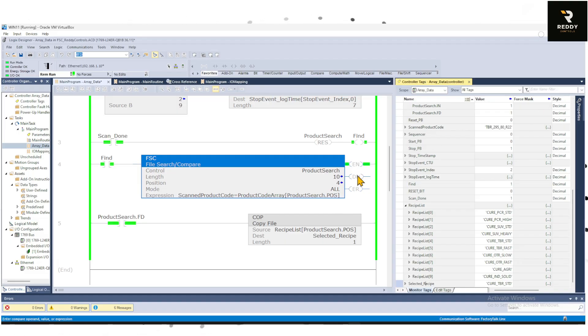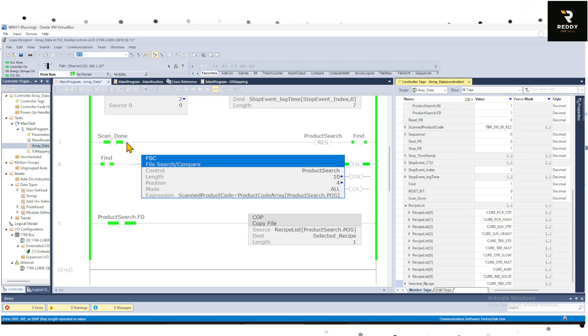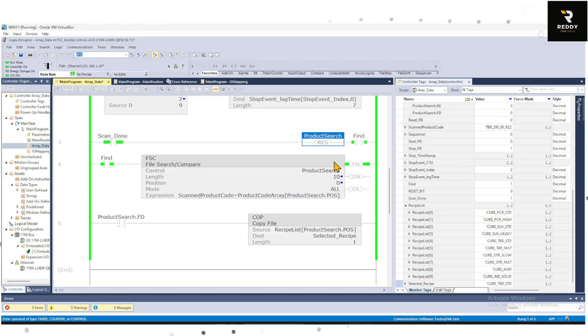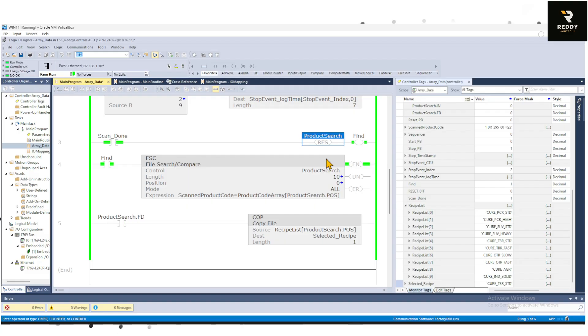So the key things to watch for is the .Found bit and the position. And once the instruction is done we move this. In the next scan we are hitting the reset. I'm just using a reset command to reset the FSC for it to retrigger. If you don't do the reset you cannot retrigger the File Search Compare instruction.